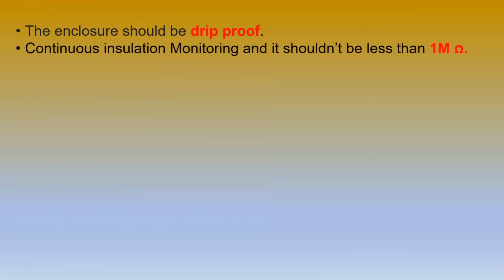If it is a high voltage system, then you have to put a red tag showing danger. The next point is the enclosure should be drip proof, that is waterproof, liquid proof, any liquid should be proof. With that, continuous insulation monitoring will be present. We have to monitor the insulation and it should not be less than 1 megaohm, as I have already mentioned.